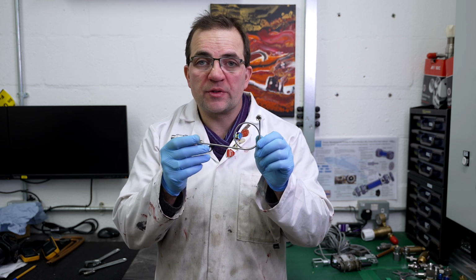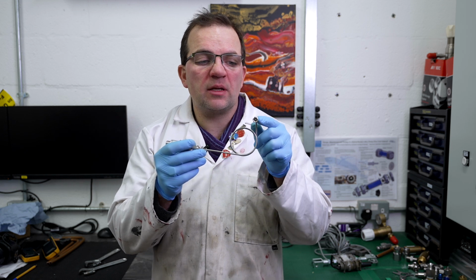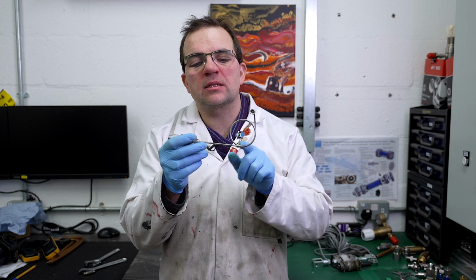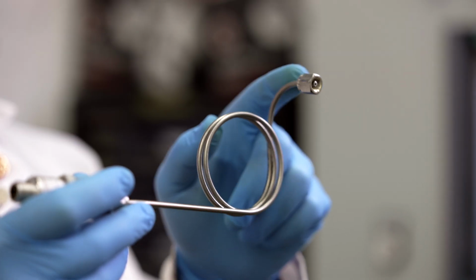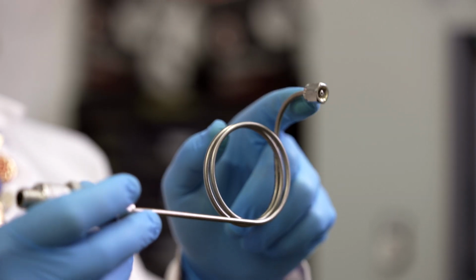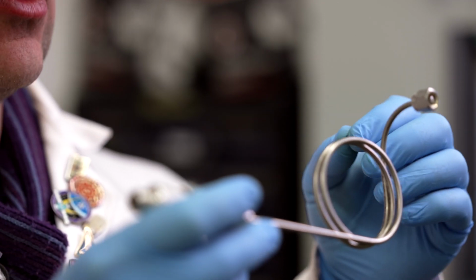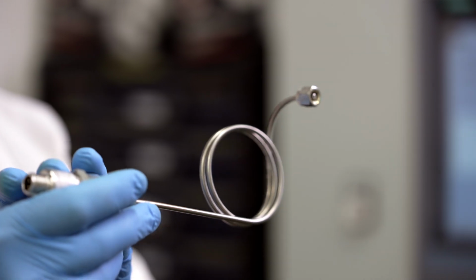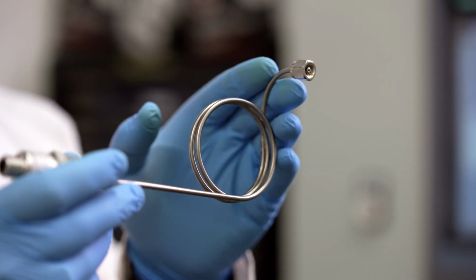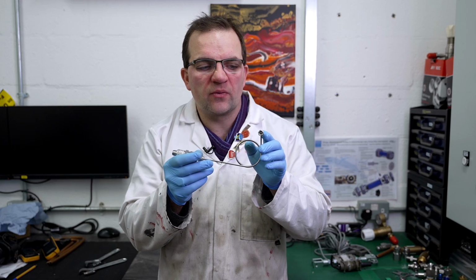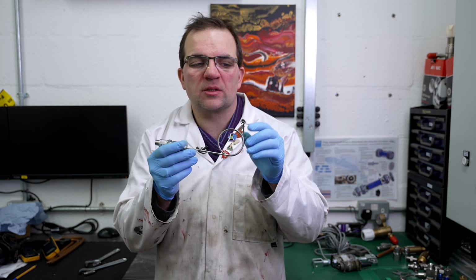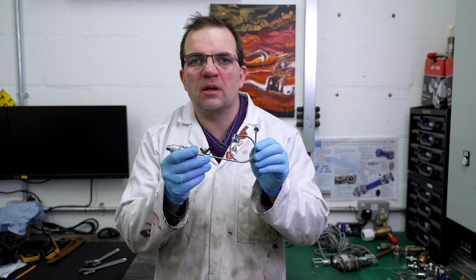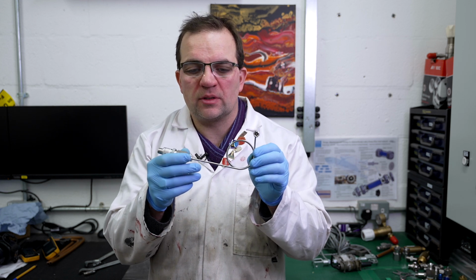Other things that we might want to think about are putting forms of lubricants or greases inside of the tube, ones which have enough viscosity to transmit the pressure waves to the pressure transducer in the system. That's another way of connecting your pressure transducers to high temperature gases as well. That lubricant then becomes effectively the thermal barrier between the two.